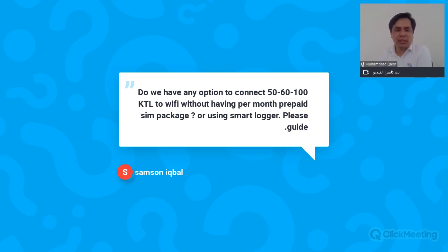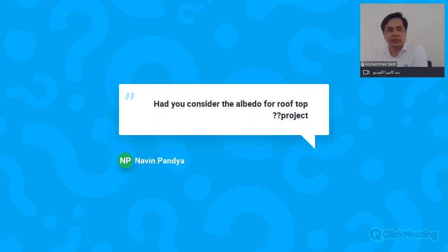Do we have any option to connect the 50, 60, 100 KTL to Wi-Fi without having a per month prepaid SIM package or using a smart logger? Please guide. Yes, you can use our smart logger to do the communication of the 50, 60 or 100 KTL inverters. You will not need a SIM for that. You can use your Wi-Fi facility within the building and do communication through the smart logger between the 50, 60, 100 to the cloud of Huawei.